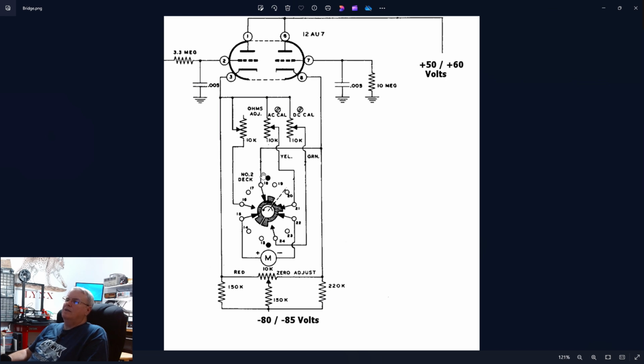That in turn ties in, and the only switch we're going to really use in the circuit description here is this one - I kind of need it to explain how the meter gets back and forth. Depending on what range you're on, the input to this meter is changed to these different pots. We're going to talk about DC for now. So for DC, this switch brings one leg on this side into the meter, and the other center tap off the DC calibration pot picks up off this leg and brings it into the meter.